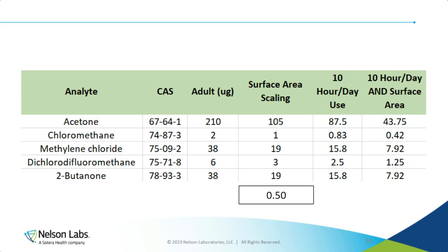Another approach we can take is the clinical use duration. This device has a maximum use time of 10 hours a day. Well, the exposure for the adult population was based off of a 24-hour exposure. We can take the 10 hours and divide it by the 24 hours to get a scaling factor of 0.417. This scales down the compounds a bit more.